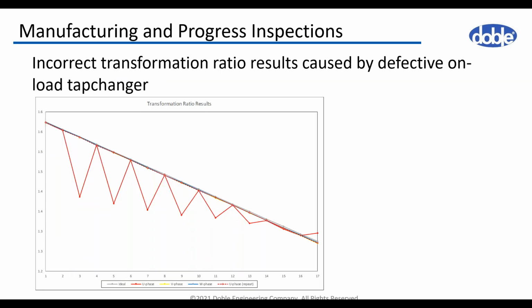I mentioned that during progress inspections, many manufacturers perform testing, and on this diagram you can see the results measured during the transformer ratio measurement, and the graph is quite unusual because of a problem related with the tap changer. In this situation, the problem was identified at a very early stage, and there was enough time to send back the tap changer and replace it by a new one in order to prevent further delay in the production, testing, and delivery of the transformer.